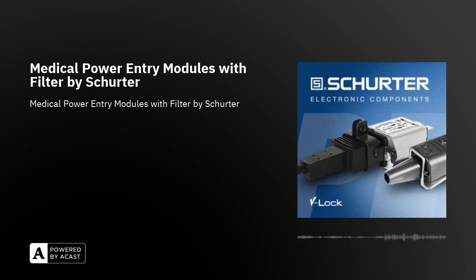As for filter and the leakage currents through PE, filter chassis, capacitors wired between the L, N and PE are Y capacitors. They produce a leakage current to PE. Current value depends on capacitance, the power line voltage and frequency. The requirement is leakage current for medical electrical equipment must not exceed 100 microamps for devices without direct operator contact, means of operator protection, otherwise known as MOOP, and 10 microamps for devices with direct patient contact, means of patient protection, otherwise known as MOPP, all according to IEC 60601-1. The solution by Schurter is power line filters for medical electrical equipment that either have no or very small Y capacitors.